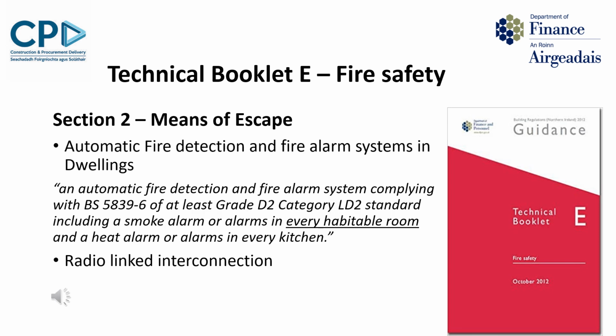In Section 2, Means of Escape and Automatic Fire Detection and Fire Alarm Systems in Dwelling Houses and Flats, the guidance has been amended to require a smoke alarm or alarms in every habitable room, as opposed to the previous requirement of the principal habitable room. So this is where the new definition of habitable room applies and will mean smoke detection in all rooms, bar kitchens, utility rooms, bathrooms, shower rooms, dressing rooms, storerooms, or WCs.